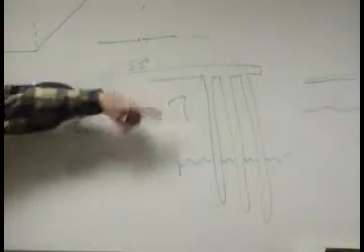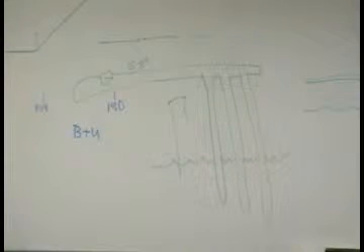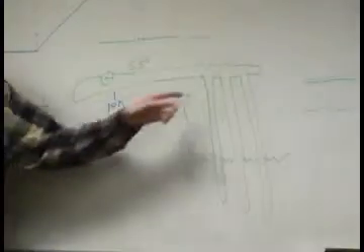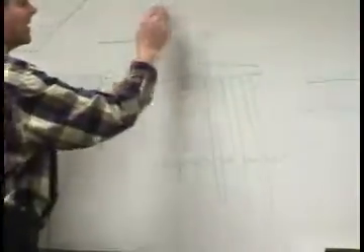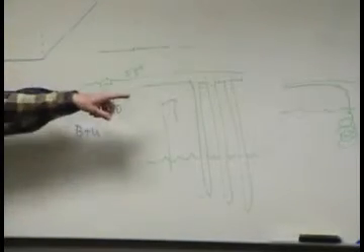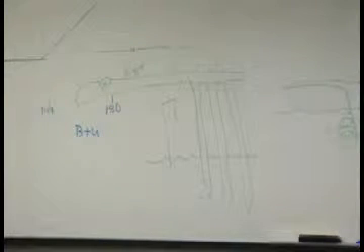One of the problems is you get all those wells piped together out there, and you send a pipe down under the ground, and this big pipe comes back out of the ground. Which ones of these are airlocked? How do you know? When they do their grids like that, I think they have like 8 to 10 wells per loop. And they'll all come back into a pit where they're all tied together and come out. So it's really tough to know, are they only getting good flow through half of their wells? They don't have any good way of figuring it out right now. They're looking at putting some flow sensors on each one of these laterals to see if they really got GPM going through them or not.